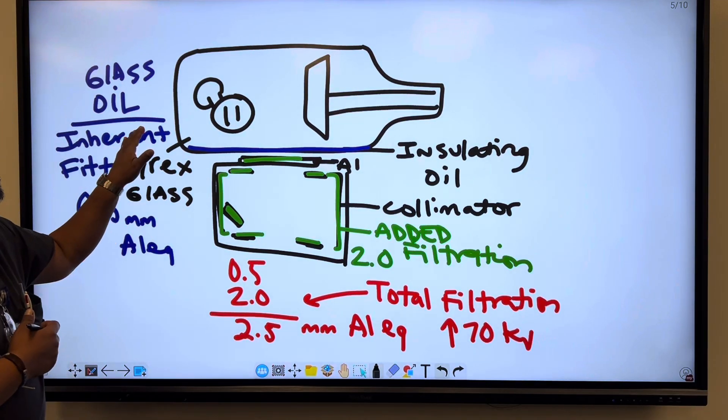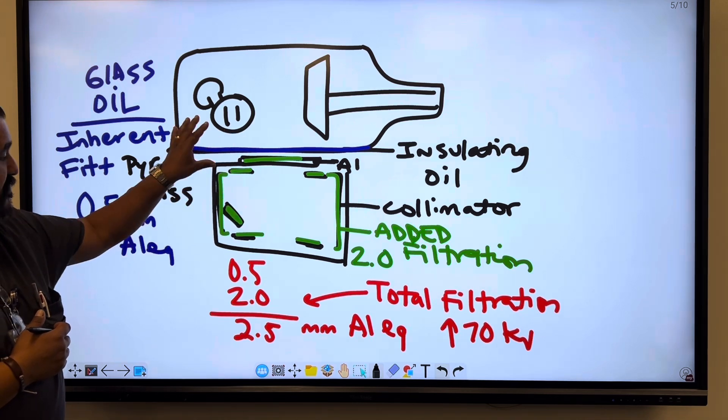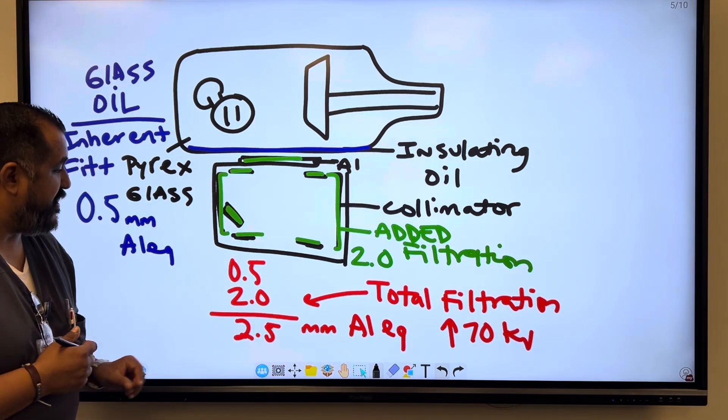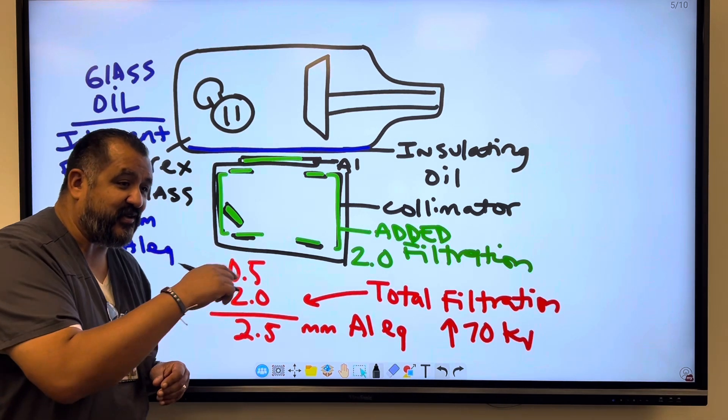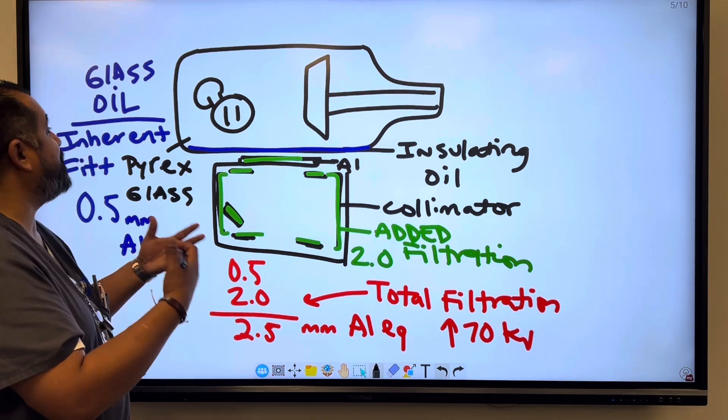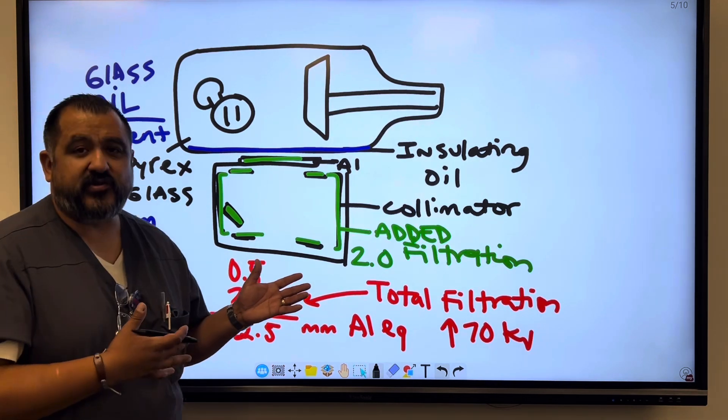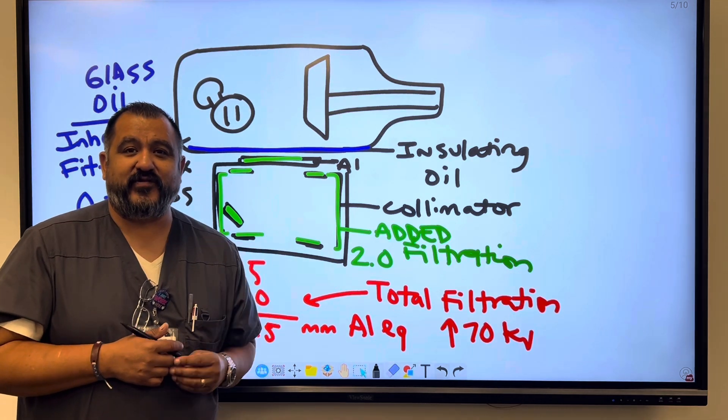Again, we have inherent, we have added, and if you add those two together, we have total filtration. And for any machine that operates above 70 kVp, under NCRP number 102, we have 2.5 millimeter of aluminum equivalent. Again, I'm hoping this quick little tutorial is going to help you understand inherent, added, and total filtration.